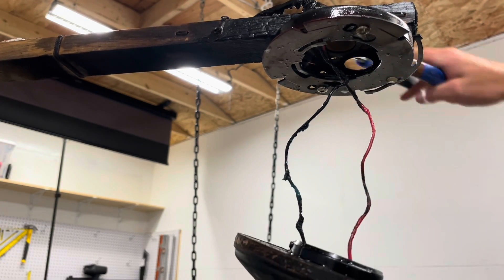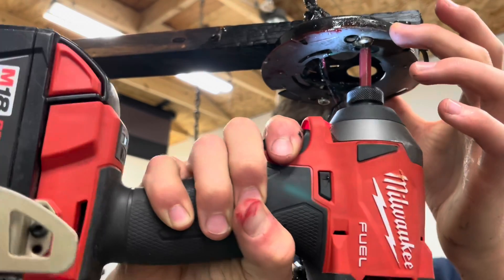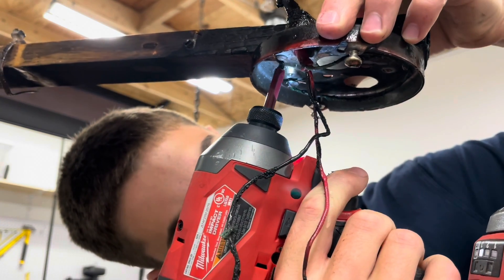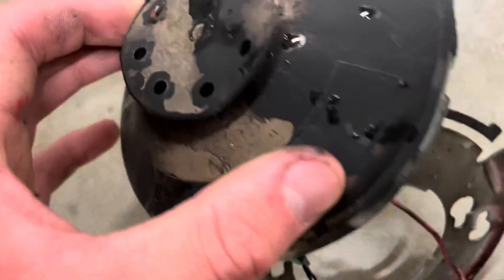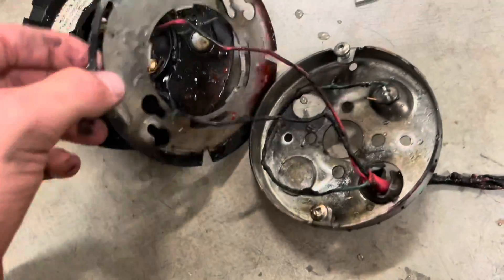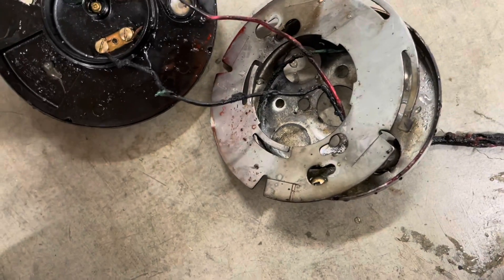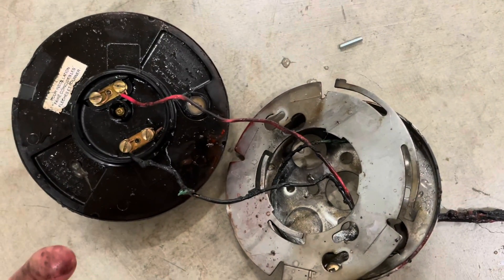Maybe I'll leave it intact and cut the fire alarm wire back here. So, as a close-up, here is what's left of the detector. This plastic bit here isn't even that melted. That's a little crispy. Our wires are pretty melted up, and our connectors, obviously, are pretty melted. Heating it up anymore wouldn't make a difference — it was hot. As much happened as would have happened there. I don't think there would have been much more that would have happened proceeding to heat it up other than things melting down.